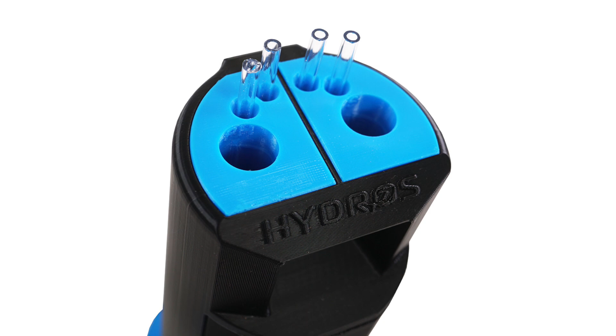It also, that material is on the lines in the back that go from the reagent line, the fill line, and the drain line, because I've had issues when I'm trying to calibrate my probe, and I grab the probe out and I'm calibrating, I put it back in, and when I grabbed it out, I probably, with my knuckle or something, pulled out some of the line, and then I'm getting strange readings, like really high readings. I'm like, what's going on? And then I go in there, it's like, oh crap, I pulled it up, so I have to push the thing back. With this self-gripping material, those lines are secure there. You have to go out of your way to pull them out.